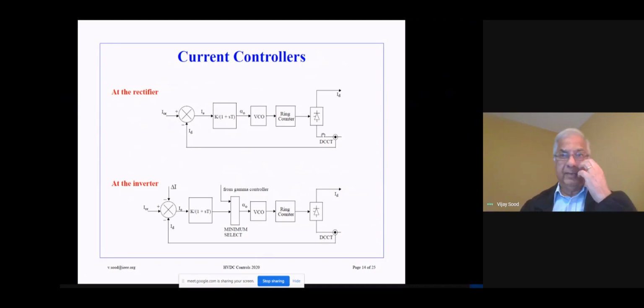We have a measurement of the DC current. There's a DC CT which is placed on the ground side. Normally it's on the ground side. It doesn't have to be, but normally it is. The measurement of the DC current is taken and then compared to the ordered current. A current error signal is generated, and the PI controller has two gains, the KP and the KI, or it has a constant K and a time constant, which is T. So this is a PI controller normally.